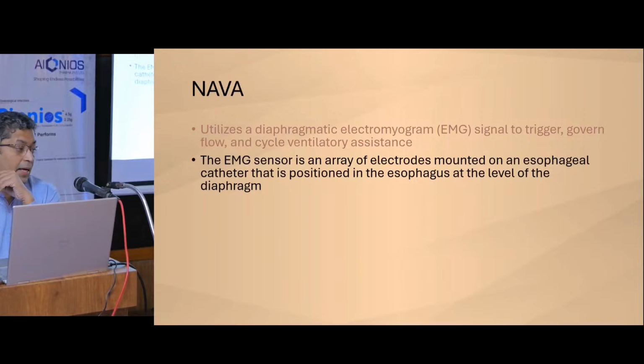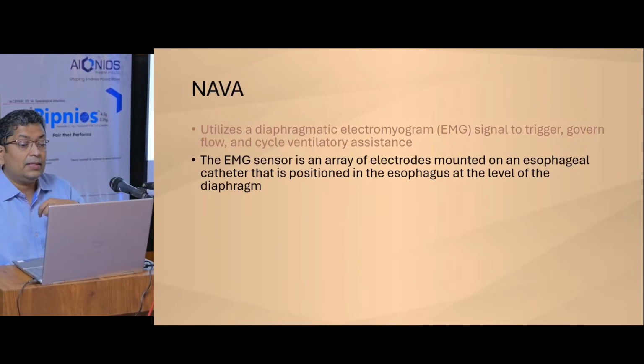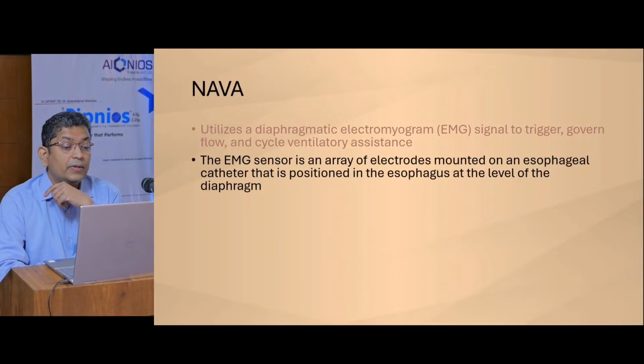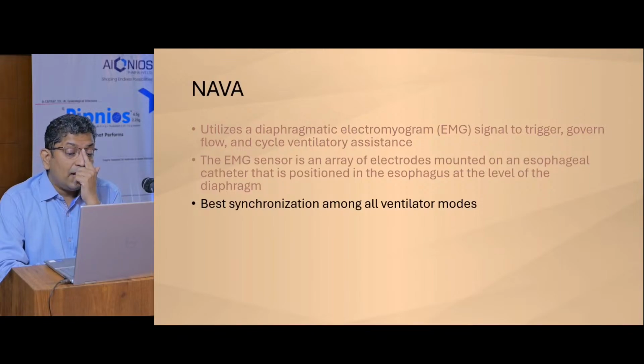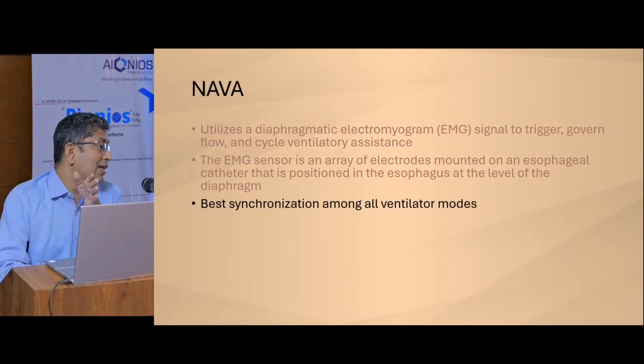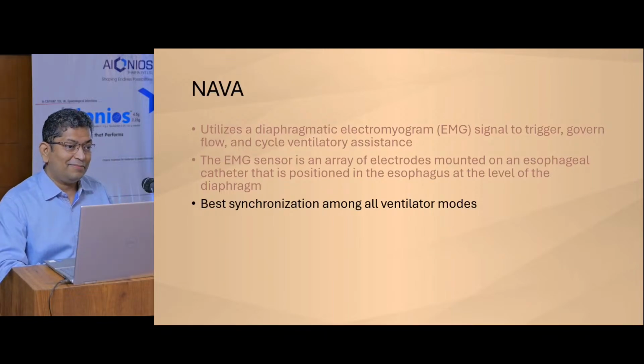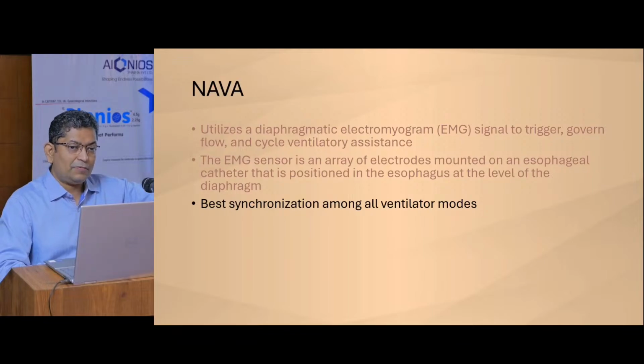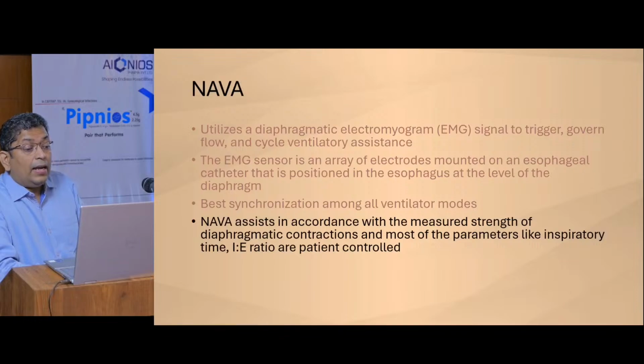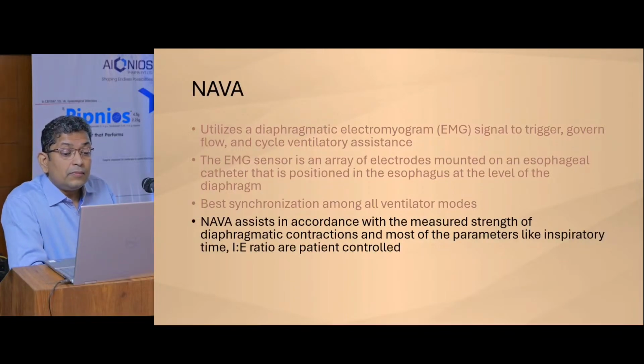It uses a sensor array in a catheter that is put in the esophagus. It gives the best synchronization of all the modes, because it is actually measuring your diaphragm and giving the breath as per your wish. So that's the best synchronization. Then it can give assistance according to the strength of your breath. So that's also very wonderful.